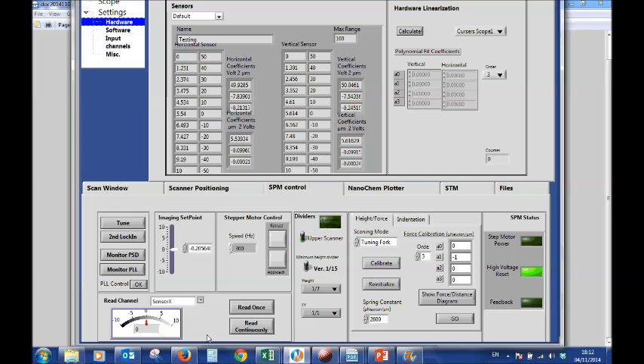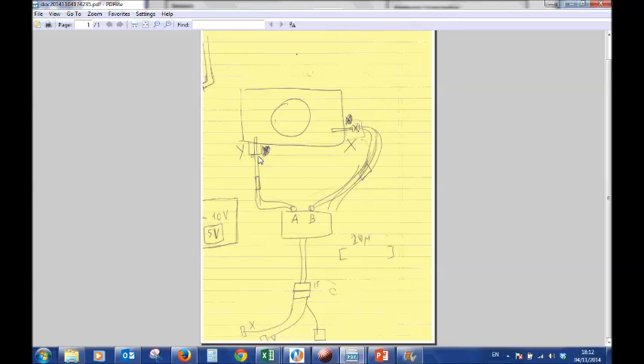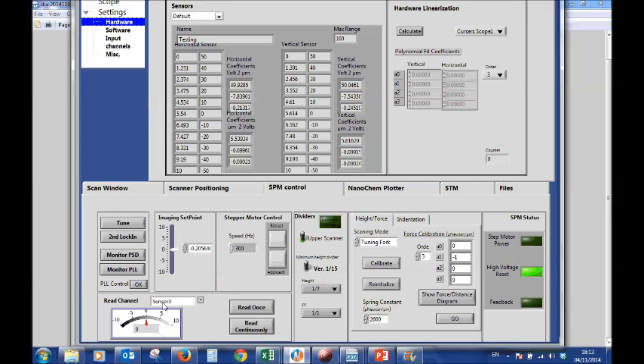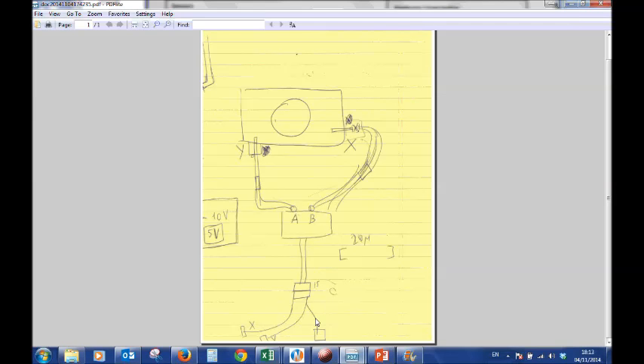And if it's not so, we have to move very, very gently and slowly with an Allen screw the sensor inside here and see how this channel is changing. So do it very, very slowly, because we don't want to harm that sensor, and make sure that it's going in the correct directions toward the 5 volts. Now, in this direction, it's a little bit more complicated, because there's a stepper motor around here. So you might have to cut the Allen key in order for it to fit in the area to adjust the sensor.